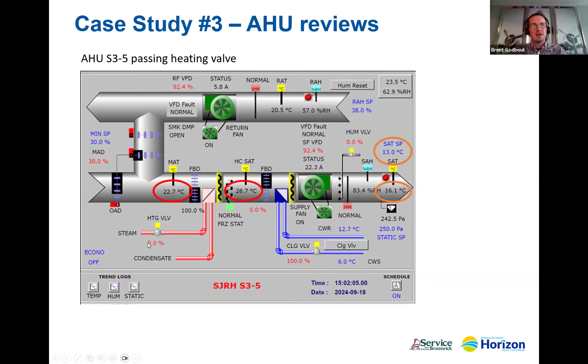On top of that, our cooling coil valve is cranking at 100, so maxed right out, and we're not meeting our set point. Our set point is 13 degrees, and we're only getting it down to about 16 degrees, so we're not meeting comfort levels within the hospital. So my first indication is it's a passing heating valve. Must be some leakage going through there.